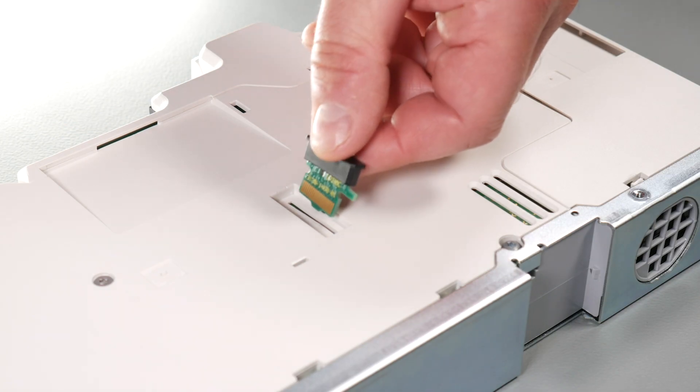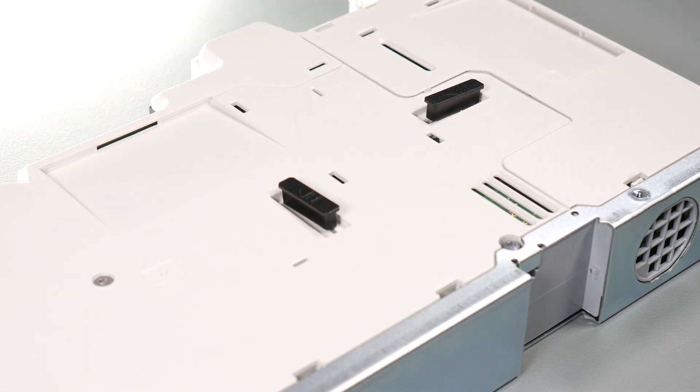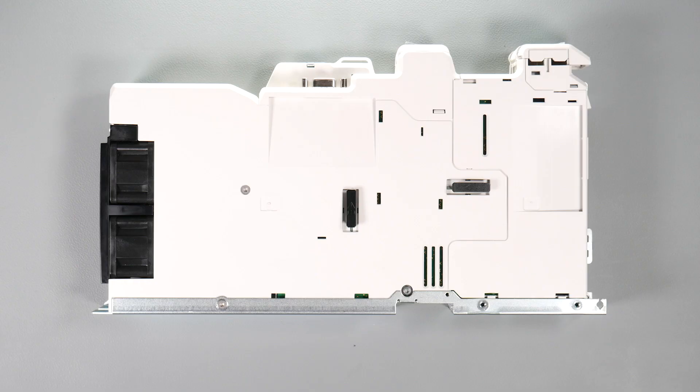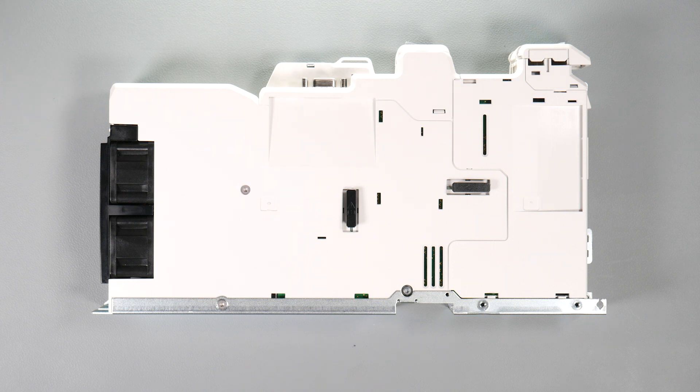Care must be taken when handling the option module interface card to avoid contaminating the gold contacts. Gold contacts must not be touched directly. Only handle the interface card using the protective cover provided in the mounting kit.